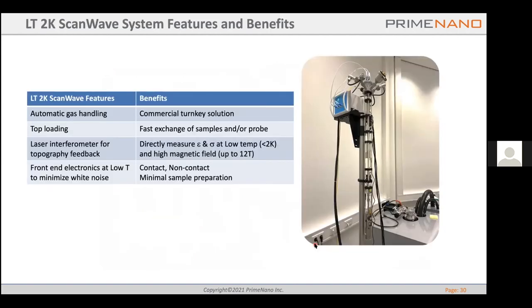So let's talk about the low temperature scan wave system. There are three kinds of low temperature systems. The first one is the 2K system, where sMIM is integrated into a cryostat that can go below 2 Kelvin. It can work with a wet system, or with a dry system with a compressor and an automatic gas handling system, and it's a turnkey solution.